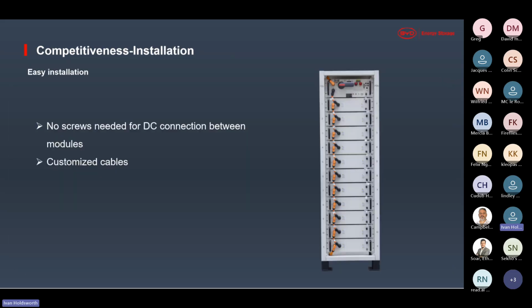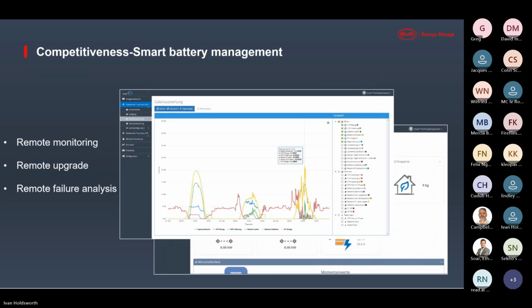And everything you see in that picture there, BYD supplies. So it'll be the rack, the PDU, and your modules. And it's very, very quick to install. There's also a lot of online monitoring. It's always best to keep note of your PDU serial number and your PDU Wi-Fi sticker on the front. And then with that, you can register on the portal and you can look at your monitoring.